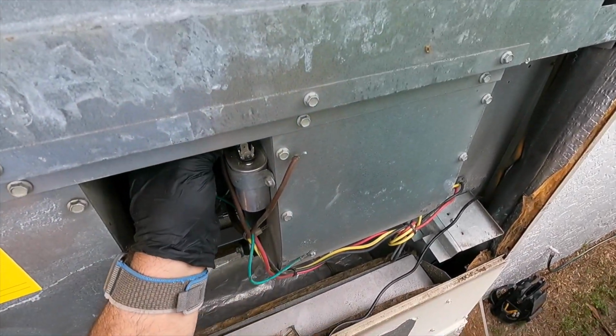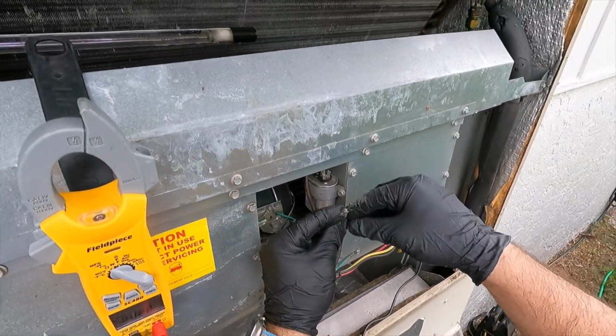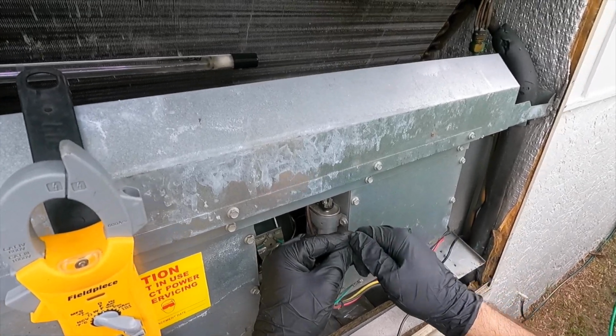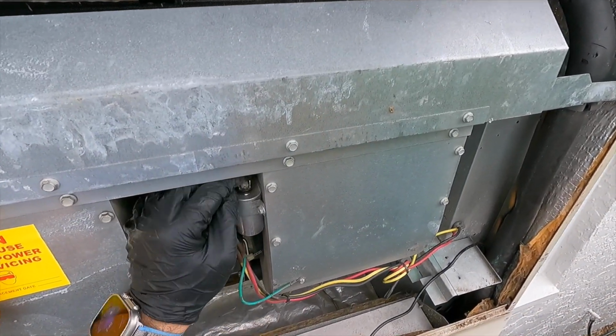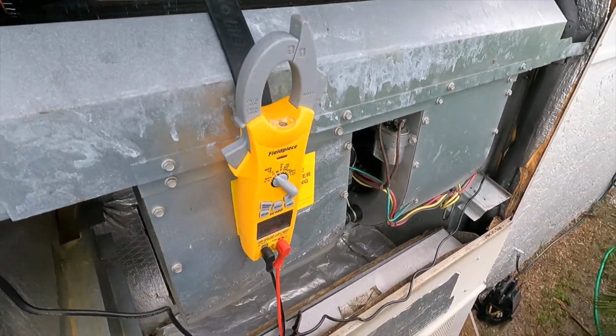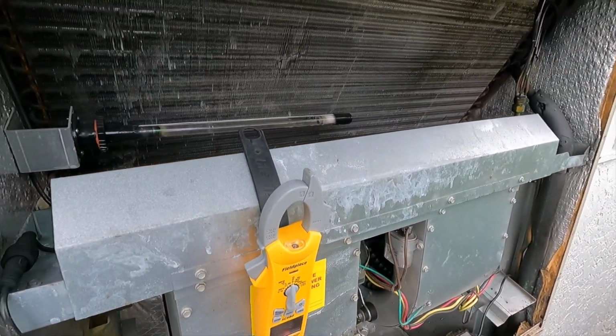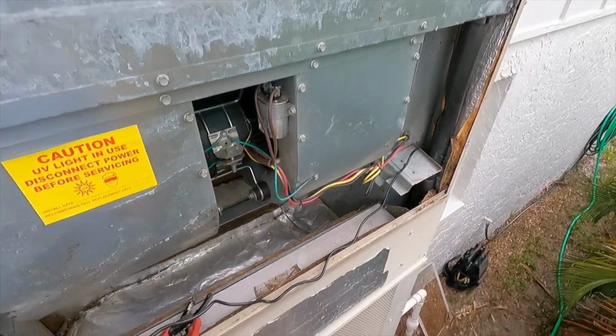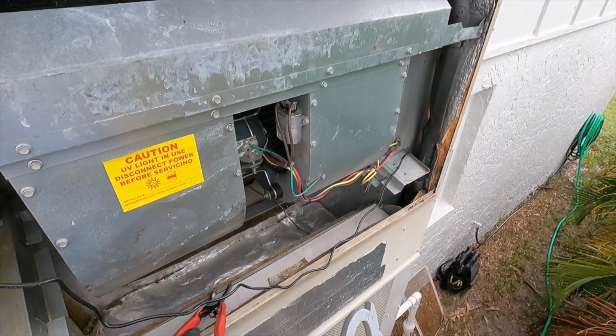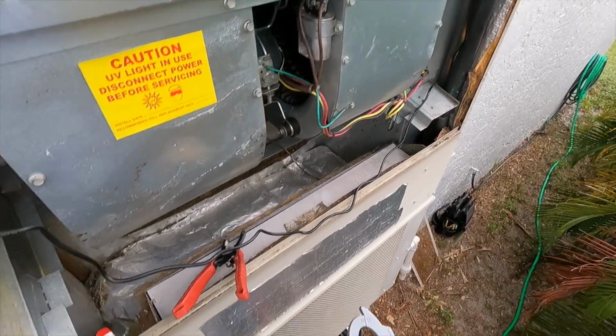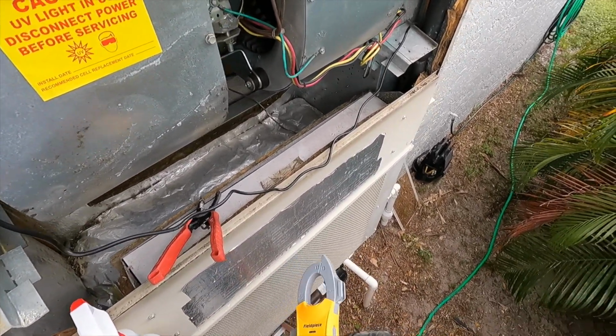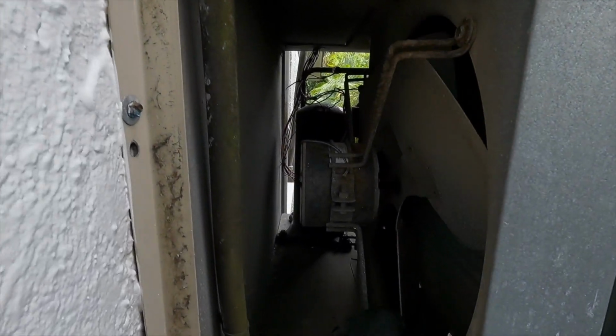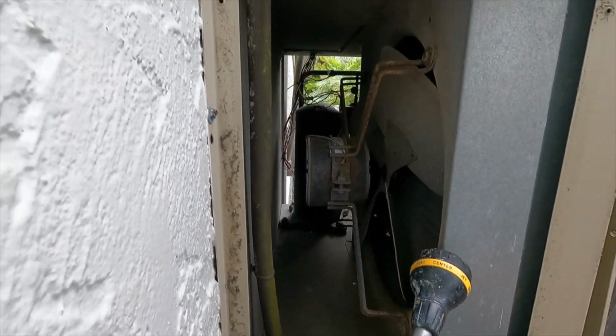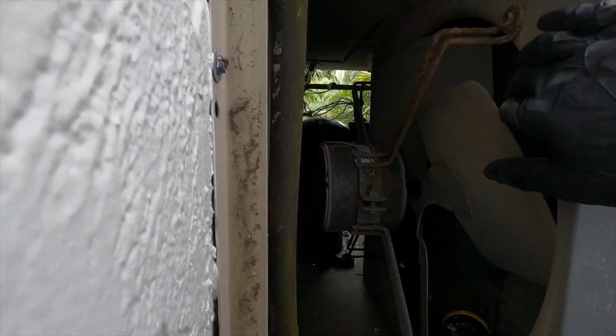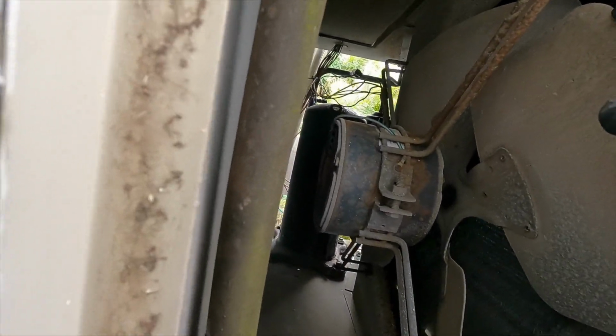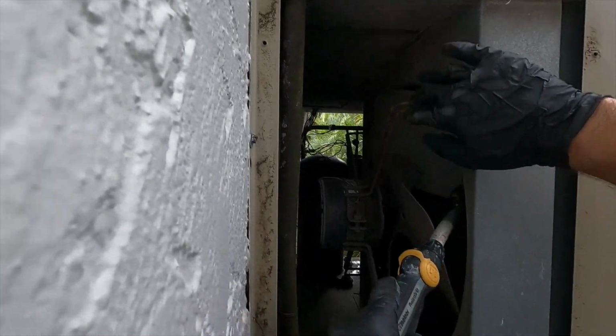With the low reading like that, we are running the risk of having a failure on the blower motor startup, so he really should replace that. We're well outside of the 3% margin on that. So all right, now that we got that going, I'm gonna go ahead and button the system up, clean up my cleaning supplies, and then we're gonna do a quick clean on the condenser coil. All right, so we're gonna go ahead and clean this coil out. Best that we can anyways.